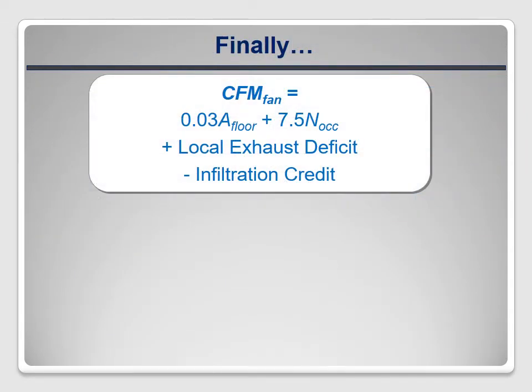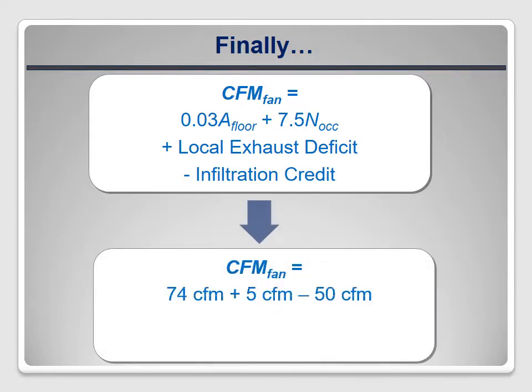We now have all the pieces needed to calculate the required fan size for this existing home. The base formula gave us 74 CFM total desired ventilation rate; the local exhaust deficit was 5 CFM; and the infiltration credit was 50 CFM. Combining them: 74 + 5 − 50 = 29 CFM. We need to install a fan that can provide at least 29 CFM of continuous ventilation.